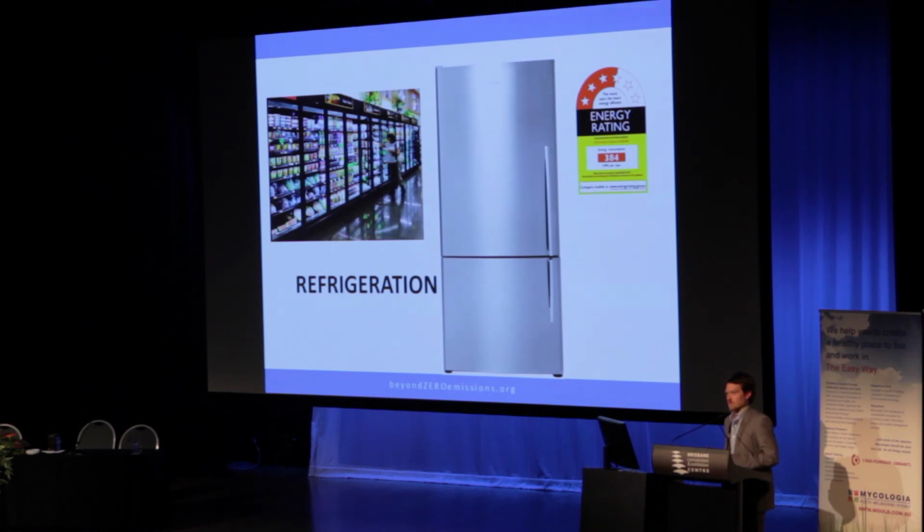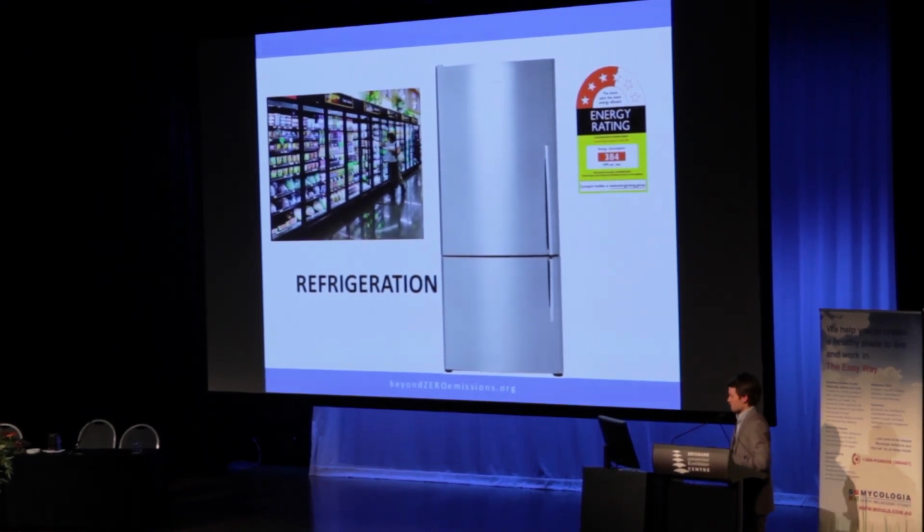But for commercial, supermarkets are really where we think there's a major opportunity, and it's not really been explored because people are worried about the impact on sales. But doors on display cases is really significant. It can have a significant reduction when you consider that refrigeration in a supermarket accounts for 60% of a supermarket's energy consumption. Putting doors on a display case is kind of a no-brainer. It stops you pumping cold air into the aisles, which is offset through either heating from underneath the fridge or downlights warming the customers as they walk past. It's a very inefficient system. Plus, looking at regassing with CO2 is another really substantial opportunity here.